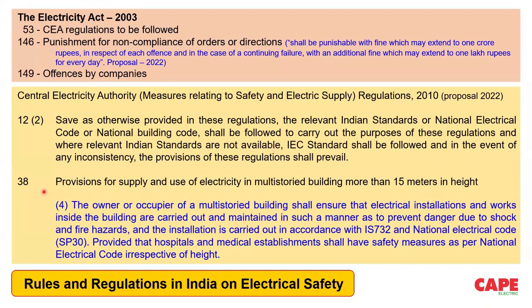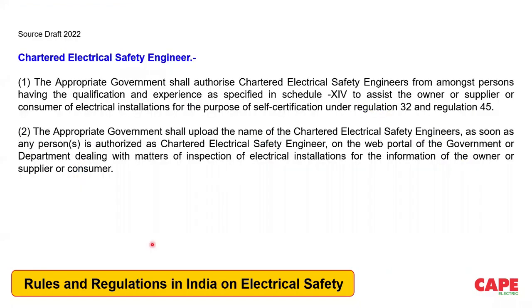For example, one of the regulations talking about consumer premises was regulation number 36 earlier. Now in the new proposal, it's regulation number 38. It says the owner or occupier of a multi-storied building shall ensure that electrical installation and works inside the building are carried out and maintained in such a manner as to prevent danger due to shock and fire hazards, and the installation shall be carried out in accordance with IS 732 and the National Electrical Code. Provided that hospital and medical establishments shall have safety measures as per the National Electrical Code, irrespective of height. So probably this is new information. The new regulation says that you should carry out your design, erection, and installation as per IS 732, or compliance to IS 732 is becoming mandatory in some of the buildings, especially high-rise buildings more than 15 meters in height.